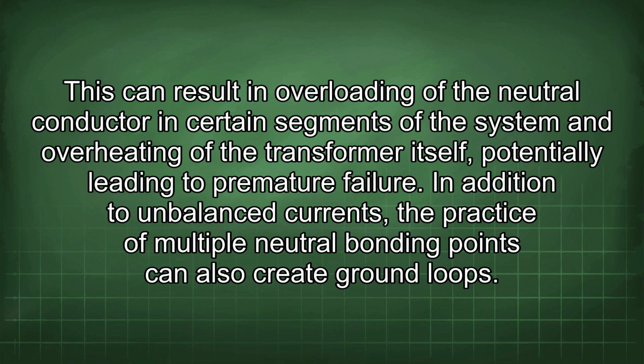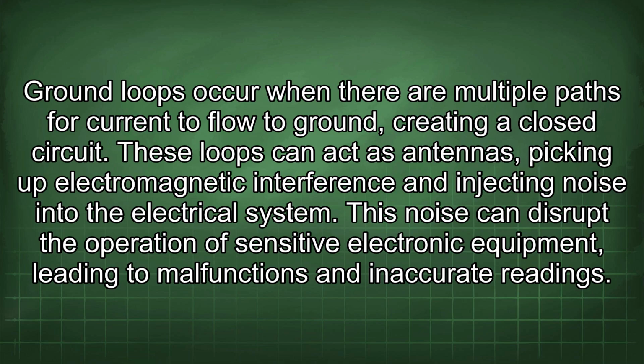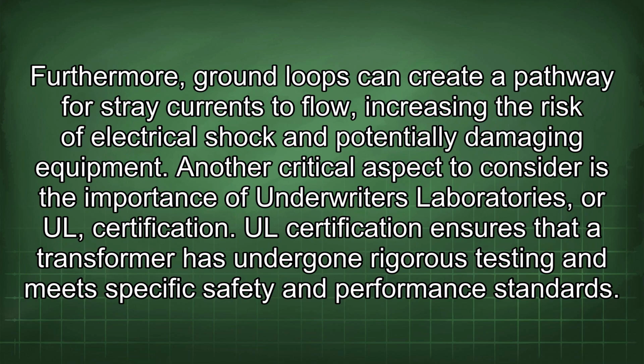In addition to unbalanced currents, the practice of multiple neutral bonding points can also create ground loops. Ground loops occur when there are multiple paths for current to flow to ground, creating a closed circuit. These loops can act as antennas, picking up electromagnetic interference and injecting noise into the electrical system. This noise can disrupt the operation of sensitive electronic equipment, leading to malfunctions and inaccurate readings. Furthermore, ground loops can create a pathway for stray currents to flow, increasing the risk of electrical shock and potentially damaging equipment.